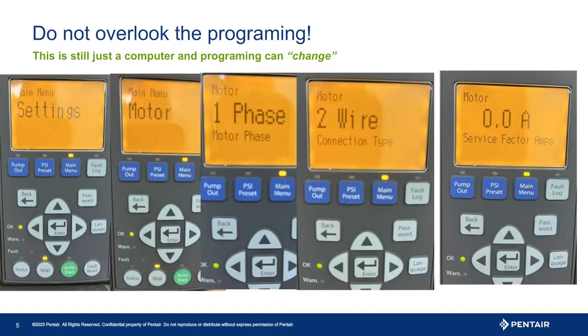To check this setting, unlock the menu if needed. The password is 4 7s. Once unlocked, the first menu you will see is Settings. Scroll down using the arrow key to bring up the motor menu. Press Enter and scroll down, proofing the motor settings. You will first see motor phase, then type of motor. Third thing you will see is the amp setting. Proof this to ensure the setting is correct and save. Using the arrow keys will change position and value, pressing Enter will save. Once the amps are proofed, press the status key to quickly exit to the main screen.